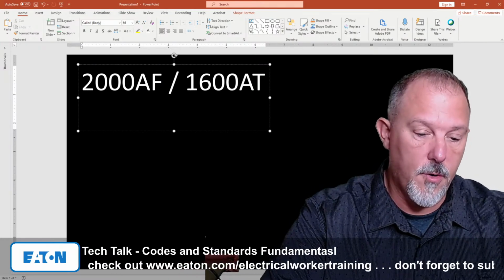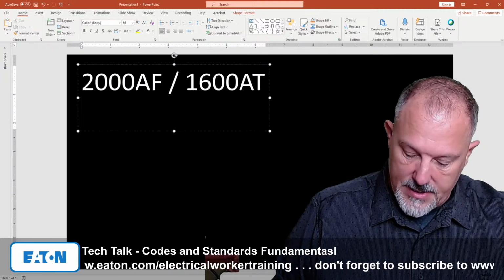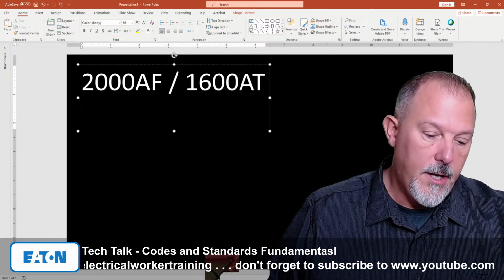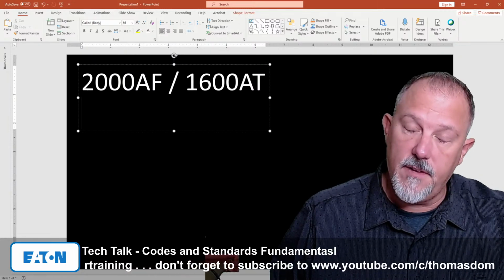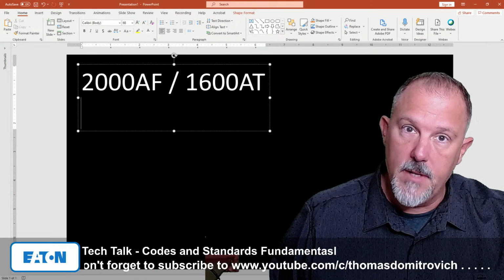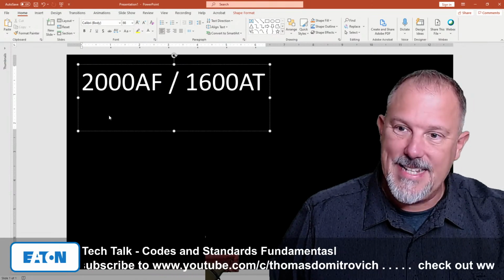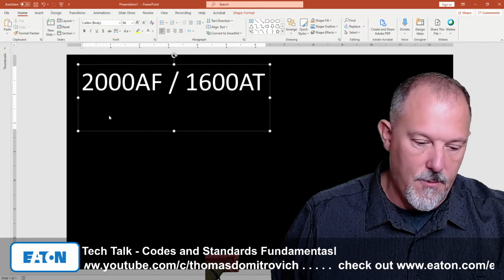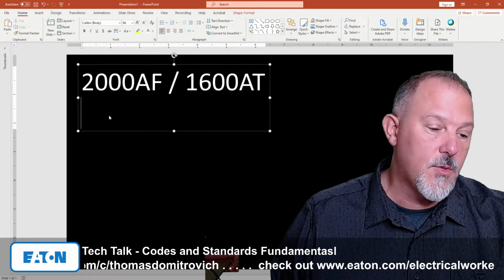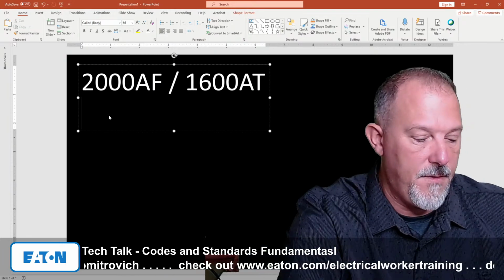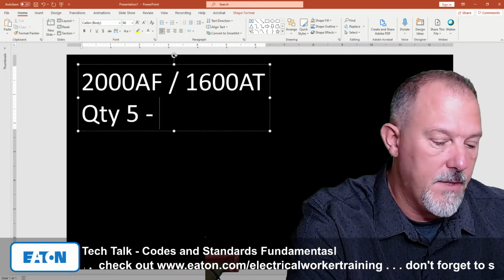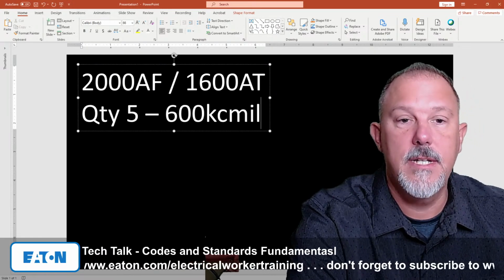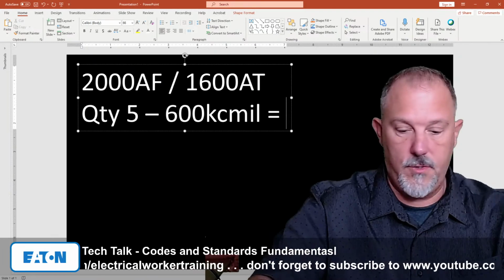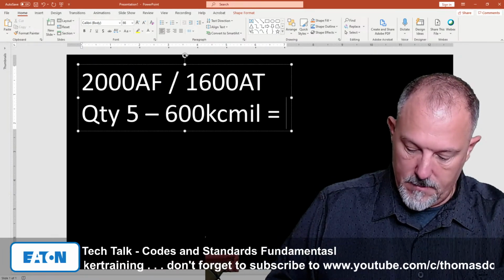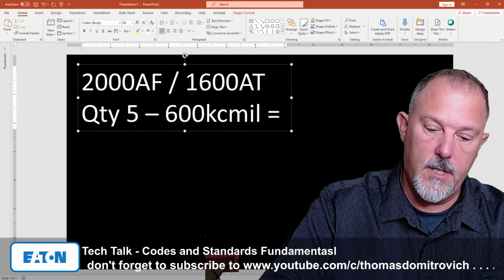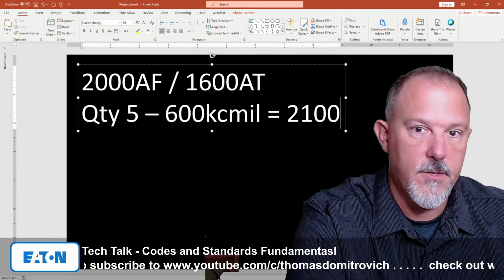2000 amps worth of conductor, if I divide 2000 amps and let's say I do a 600 kcmil, it has an ampacity at 75 degrees C. Why am I using the 75 degrees C ampacity? Because it is the rating of the breaker. Hey, Felix. TSDN, Technical Social Distancing Network. So 2000 divided by 420 is 4.76. So I need quantity 5, 600 kcmil conductors, which is equal to 5 times 420 amps. That's 2100 amps, 2100 amps.